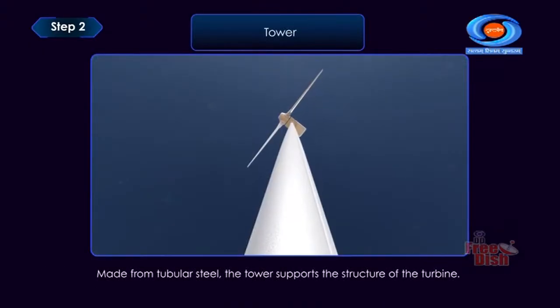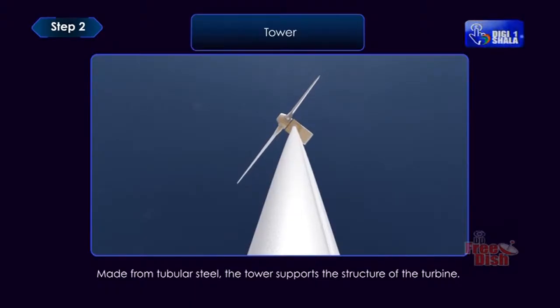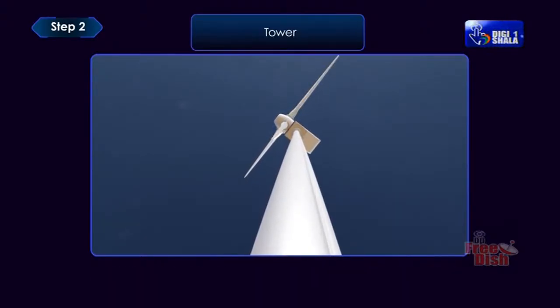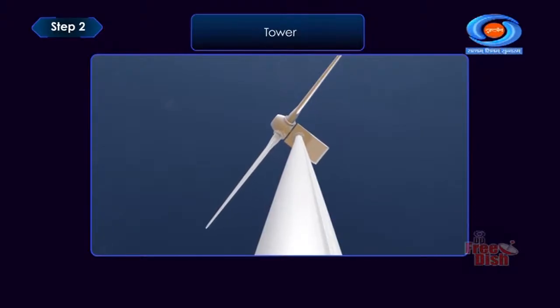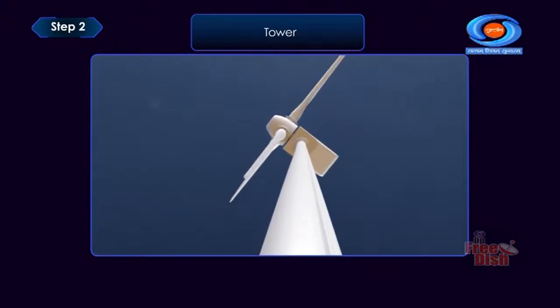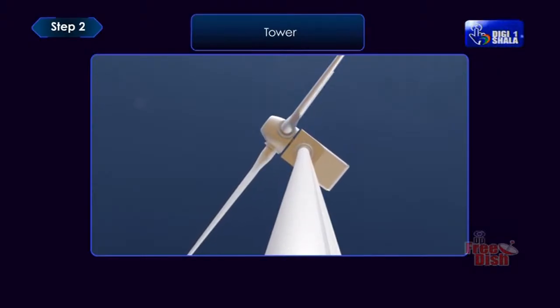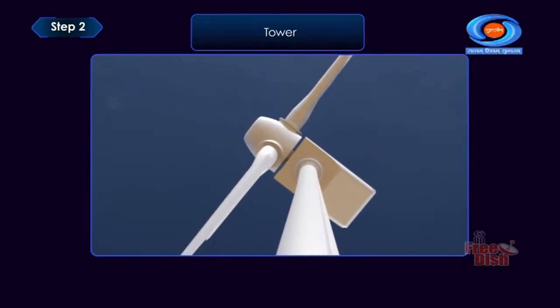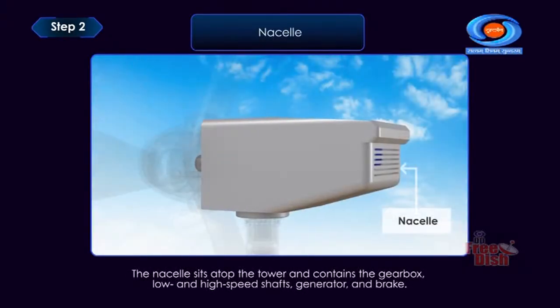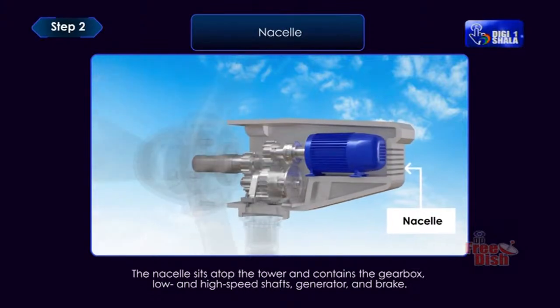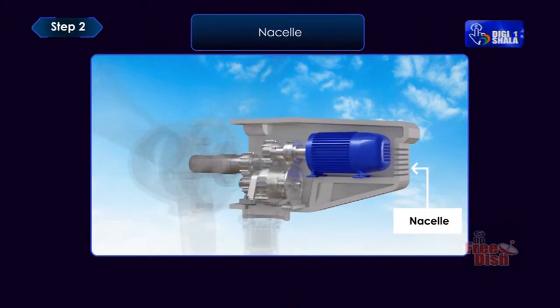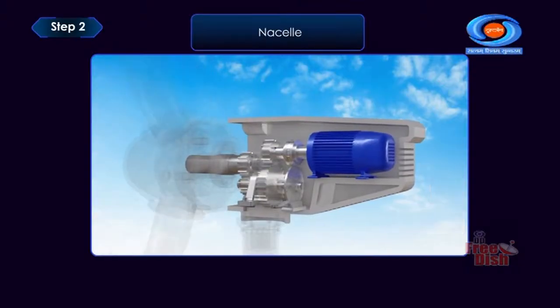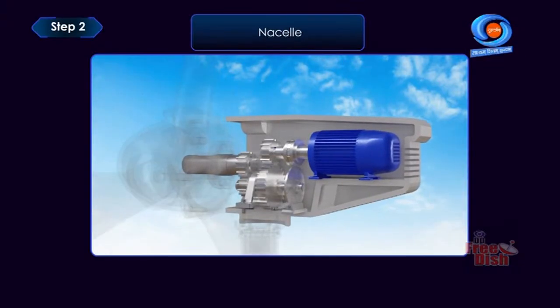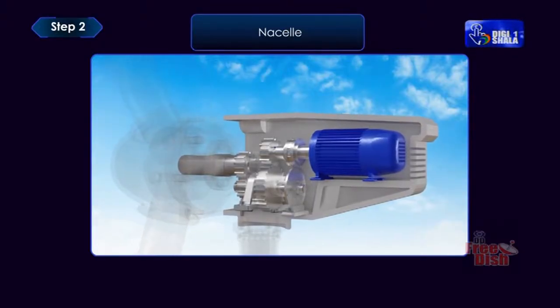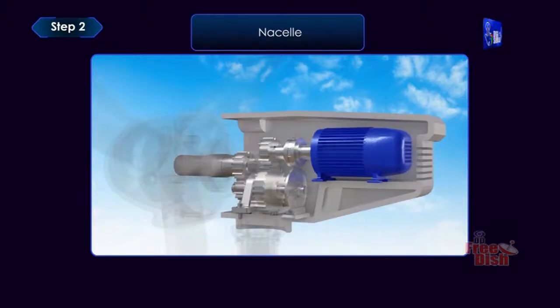Tower. Made from tubular steel, the tower supports the structure of the turbine. Because wind speed increases with height, taller towers enable turbines to capture more energy and generate more electricity. The turbines comprise an 80-meter tall tower and 35.5-meter long blades. Nacelle. The nacelle sits atop the tower and contains the gearbox, low and high-speed shafts, generator and brake. Some nacelles are larger than a house, and for a 1.5 megawatt turbine can weigh more than 4.5 tons.